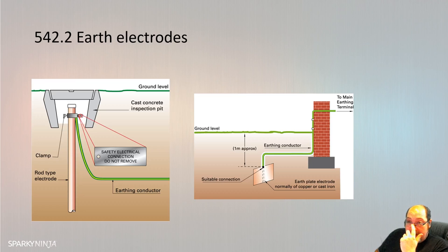If you do regular routine periodic inspections of an installation with an earth electrode, if you were to say I'll come back in 5 years or 12 months or whatever, change it to a month less or a month more, so that as you do some tests it kind of staggers around the year. Or if you can, move it 6 months, bring it 6 months prior, so that you can test the different seasons with the electrode's resistance.